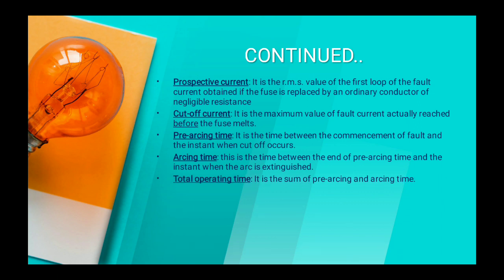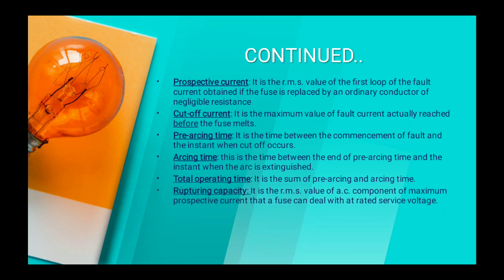Total operating time is the sum of pre-arcing time and arcing time. Rupturing capacity is the RMS value of the AC component of maximum prospective current that a fuse can deal with at rated service voltage. So it is the root mean square value of the alternating component of maximum prospective current that a fuse can handle at rated service voltage.